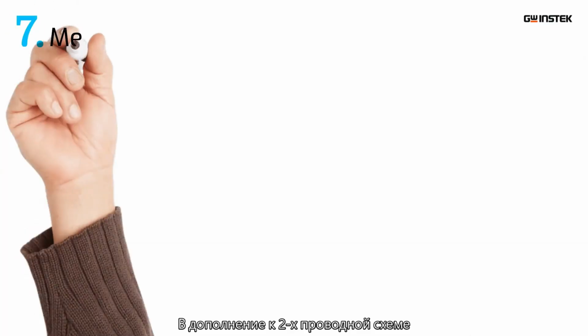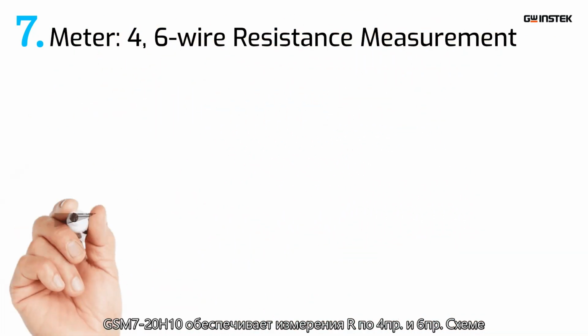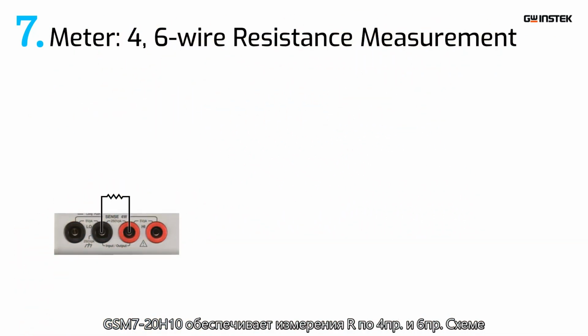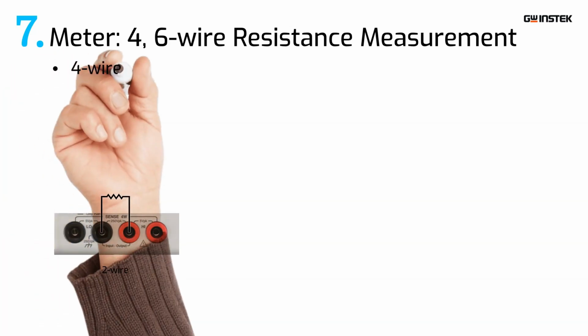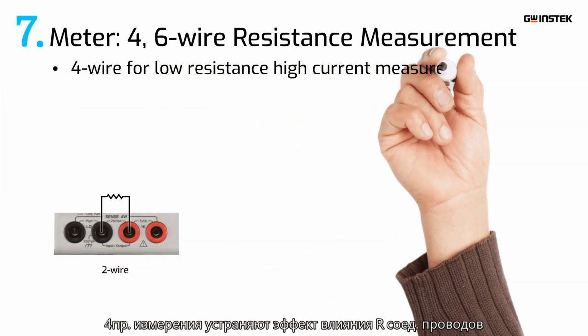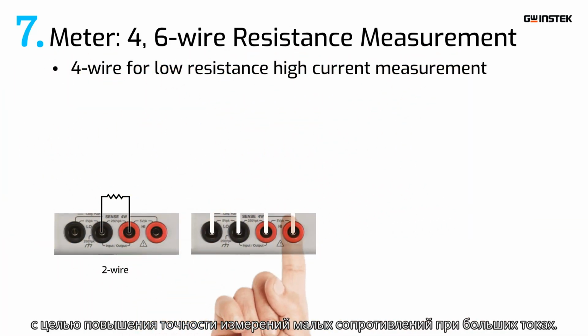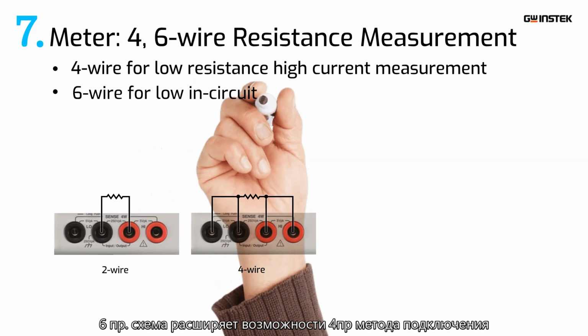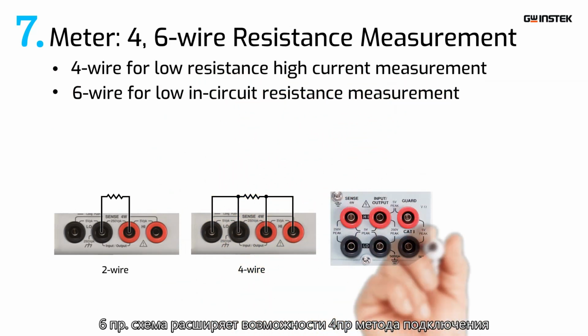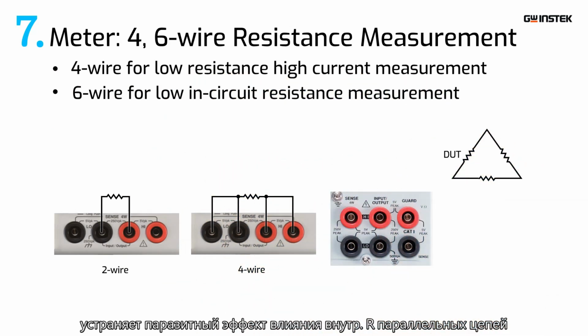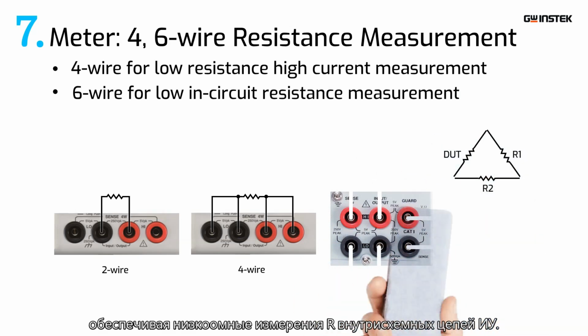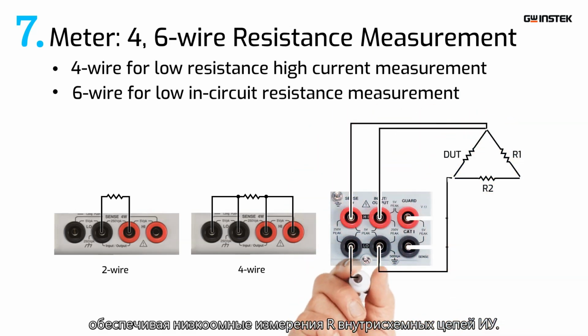In addition to 2-wire, GSM-20H10 provides 4- and 6-wire resistance measurements. 4-wire measurements eliminate the lead resistance effect to achieve accurate low resistance measurement under a high current situation. 6-wire combines 4-wire connection and guarded ohms feature to eliminate the effects of internal parallel resistances to achieve the low in-circuit resistance measurement.